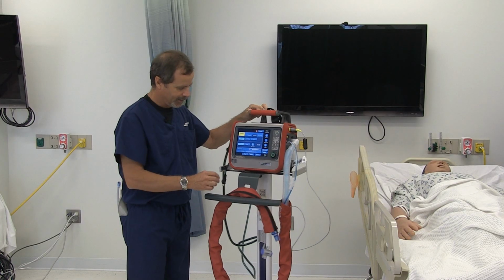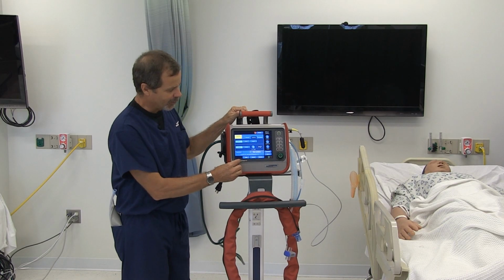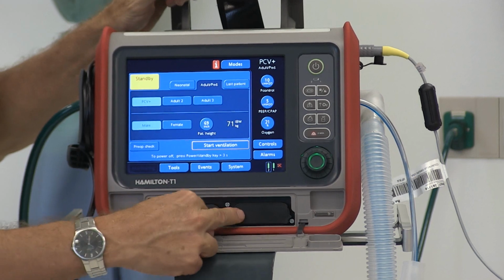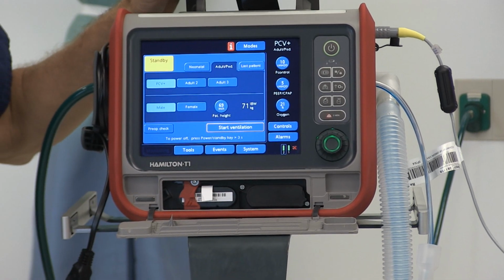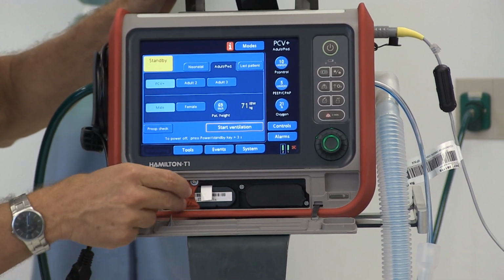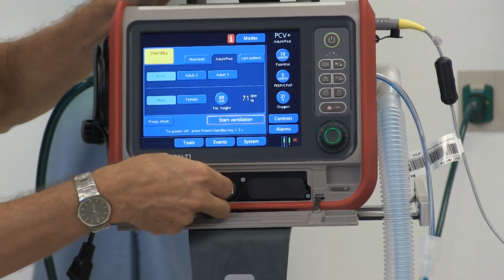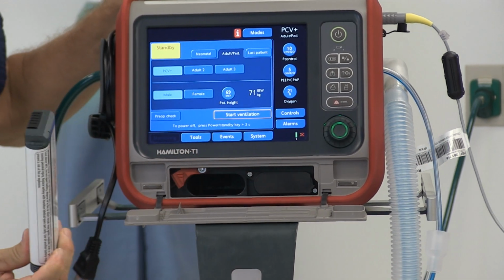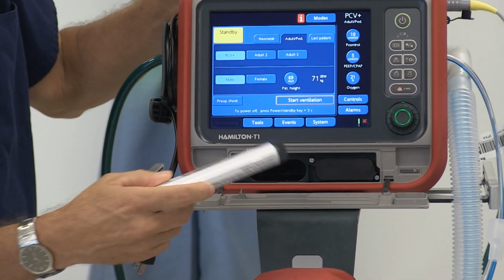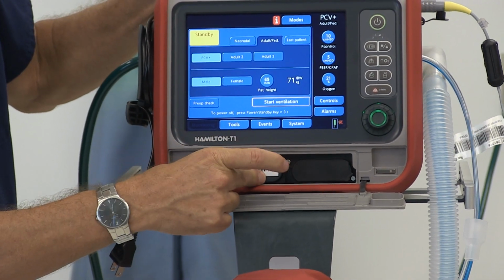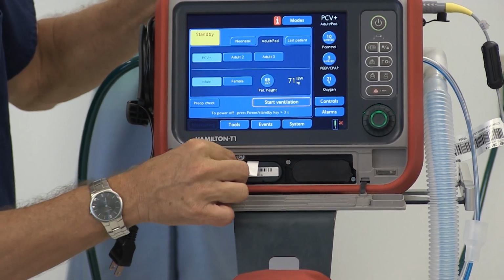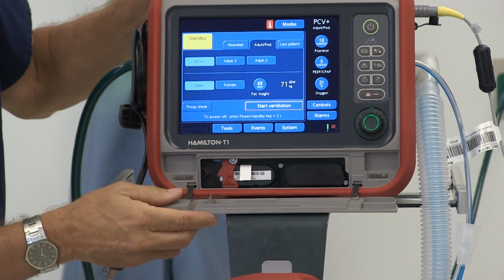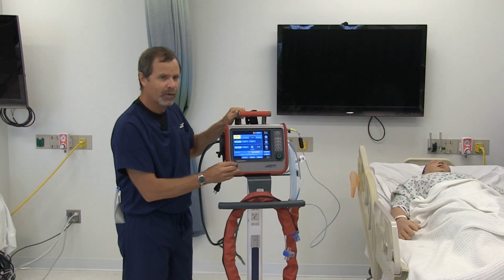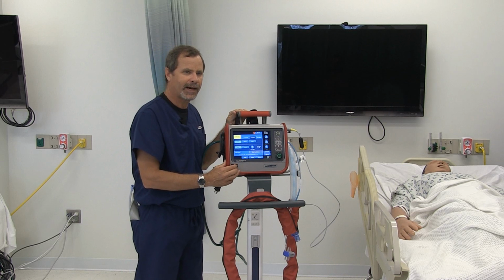Okay. Now the front of the ventilator, at the lower part, is a battery compartment. There's two batteries. This is battery number 1, it's fixed. Battery number 2 is hot swappable. I simply slide the lever to the side, remove the battery. I can replace it with a fresh battery. Reinsert, close the lever, and shut the door. With both batteries fully charged, you get approximately 9 hours battery life.